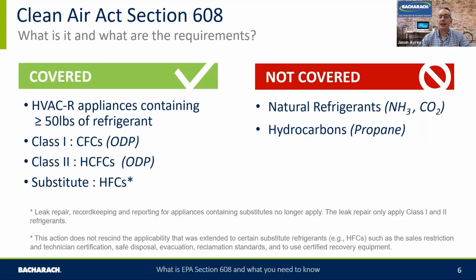But what's not covered? Very simply, everything else. We've got lots of new refrigerants coming on the market that's used out there. So natural refrigerants are currently not covered. So the likes of ammonia, carbon dioxide, and hydrocarbons as well, propane, for example. These are kind of the typical refrigerants that you may run into in terms of your organizations.